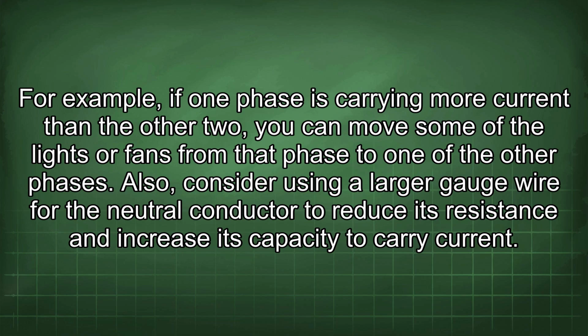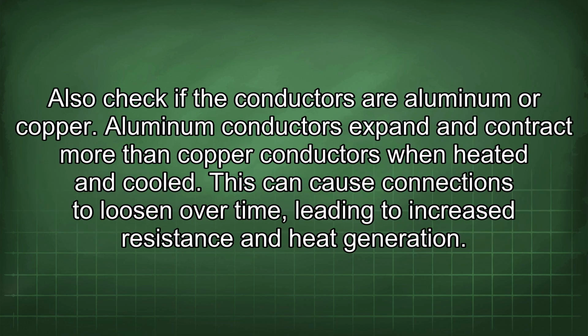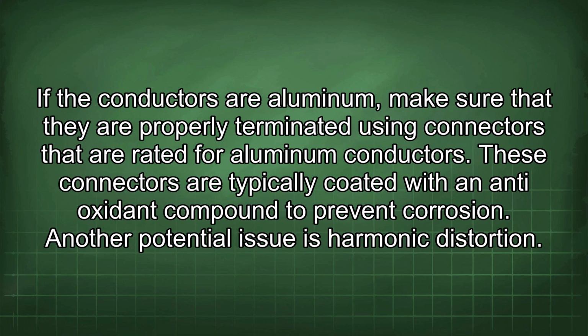Also, consider using a larger gauge wire for the neutral conductor to reduce its resistance and increase its capacity to carry current. Also check if the conductors are aluminum or copper. Aluminum conductors expand and contract more than copper conductors when heated and cooled. This can cause connections to loosen over time, leading to increased resistance and heat generation. If the conductors are aluminum, make sure that they are properly terminated using connectors that are rated for aluminum conductors. These connectors are typically coated with an antioxidant compound to prevent corrosion.